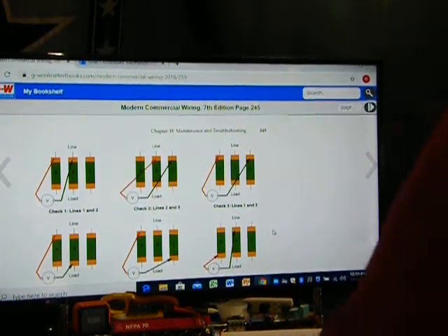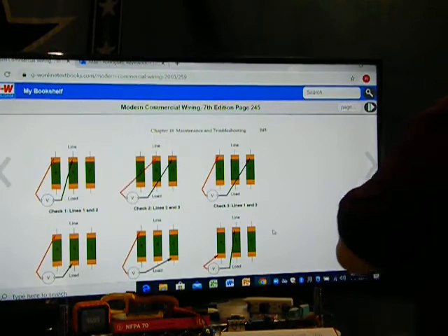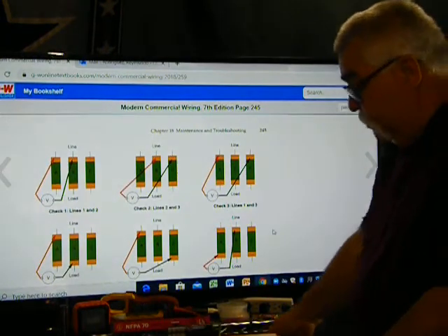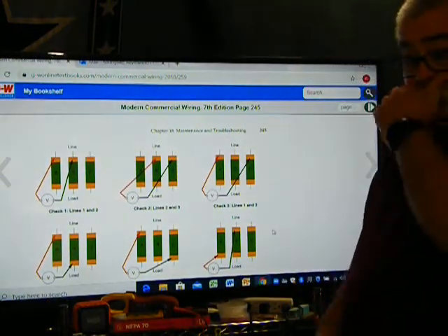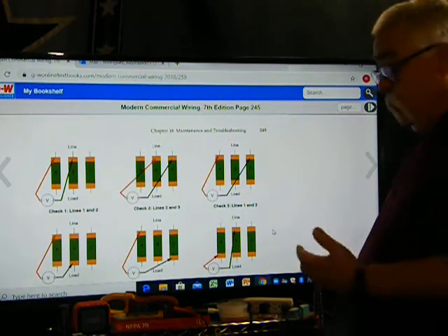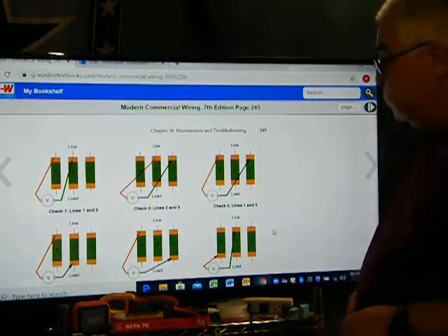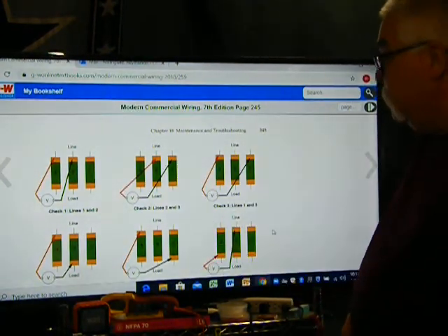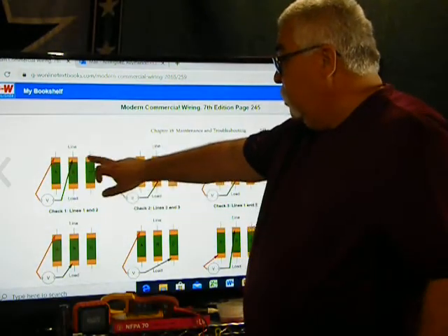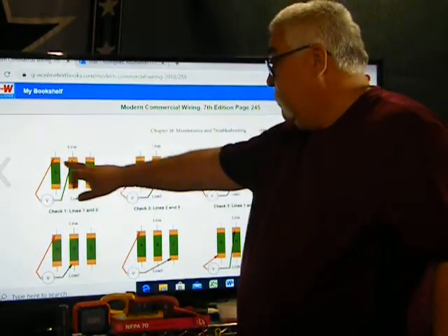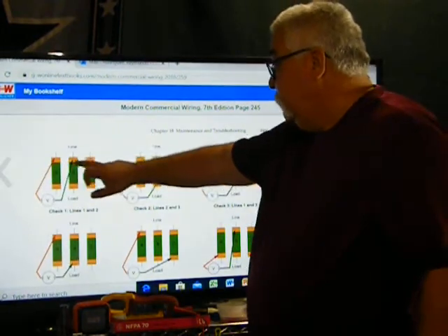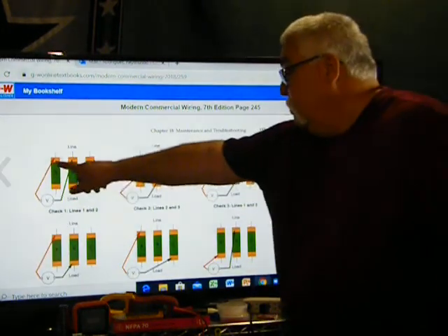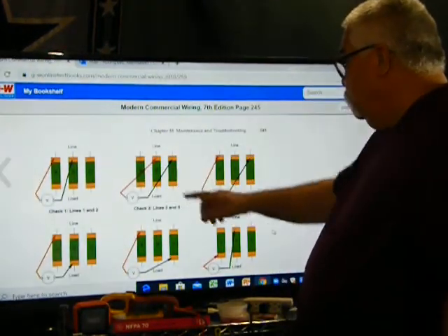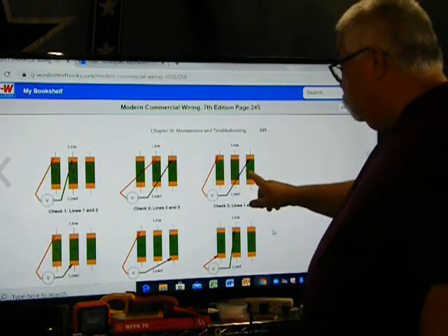Alright, this is a picture I was hoping was in the PowerPoint, and it wasn't. But when you're getting your tester, say this is at the disconnect. So you have a disconnect where your equipment's at. So you always check on the line side to make sure it's hot. Okay? Line to line, line to line. So here they're doing it A to B, and then they're doing it from B to C. Then they're going from A to C.